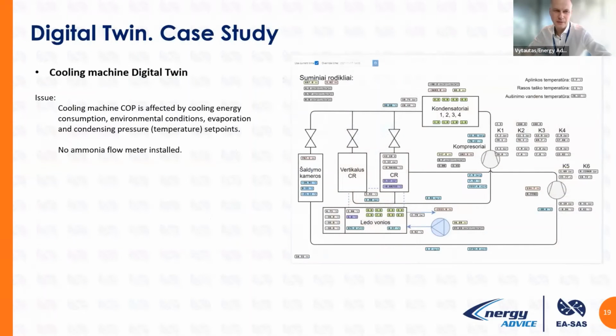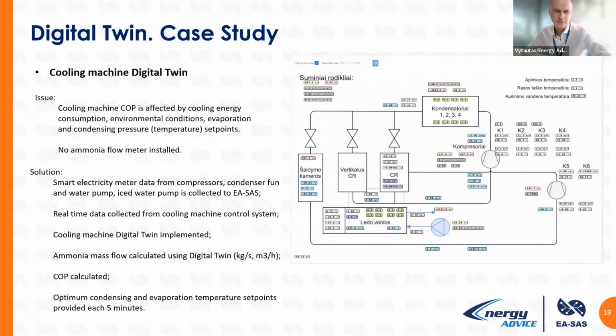Case study, a dairy company asking us. Its system consists of 4 compressors, condenser, receivers, chilled water, cold rooms at -2, you can see inside, and 2 compressors working in the loop. So it's a 2-stage system, with slightly different designs as usual. We installed a digital twin with real-time data collection, and calculated COP. We also calculate ammonia mass flow, and the digital twin calculates every 5 minutes.